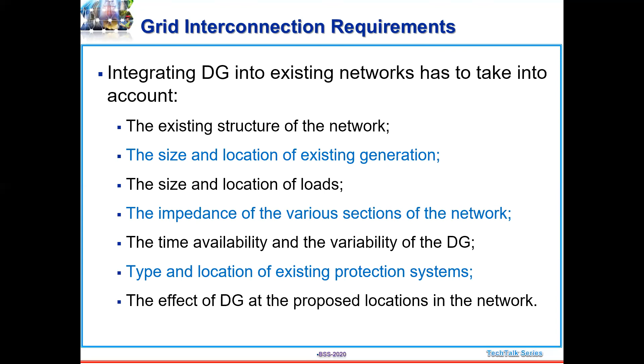The time availability and the variability of the DG has to be ensured. That's one of the important things. Then the type and location of the existing protection systems. You have to relook at the protection systems before integrating the DG. Then the effect of DG at the proposed location: whether it will increase or reduce the fault level, whether there will be voltage variations, whether there will be voltage rise or voltage dip. Those things we have to study. These are some small systems, interactive systems only. That's what is being used currently everywhere for almost all the rooftops without any battery storage.